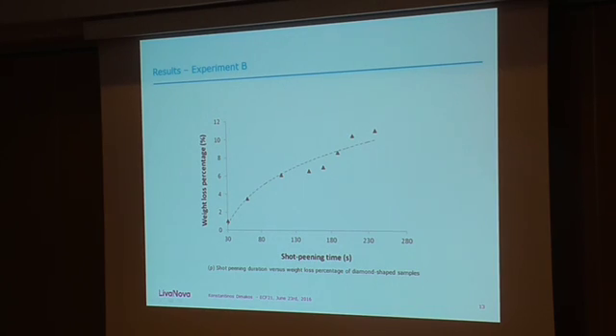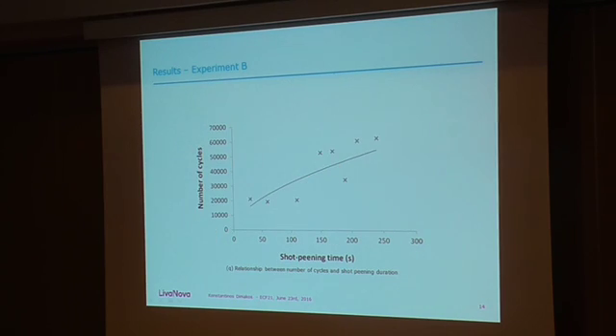Since the Almen strips are not nitinol and are steel, just in case, we also measure the weight loss percentage, because at least in my company, we have a limit, which is 8%. So we don't want to shot peen for a time that causes more than 8% of weight loss. And this is the most important graph, because we have a relationship between the number of cycles and the shot peening time. This is the sample that caused me all the problem. But at least, we know that if we peen more components, if we have more samples, we know that we can reach a saturation curve. There is a tendency here.